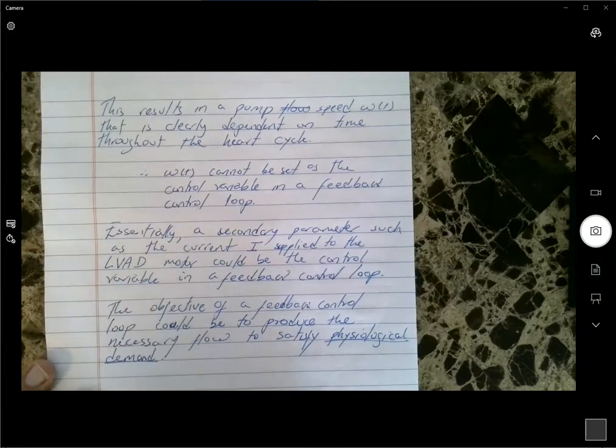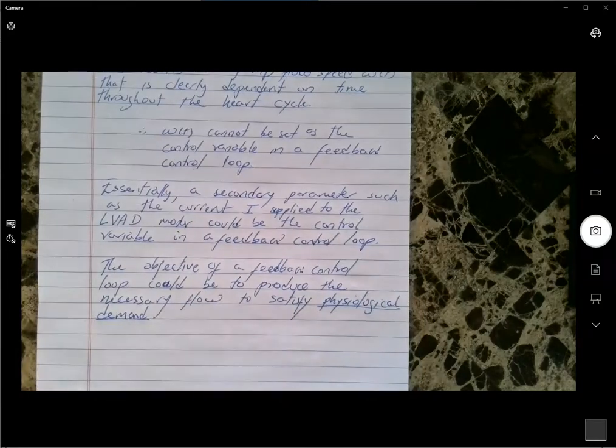Again, the physiological demand is dictated by how active the person is. If it's a low level of activity, the person doesn't need that much blood, so the pump should actually slow down. If the person is active, then it requires more blood, and the pump power should be increased, but it cannot be increased directly to the speed. It has to be increased to a secondary variable like the current.